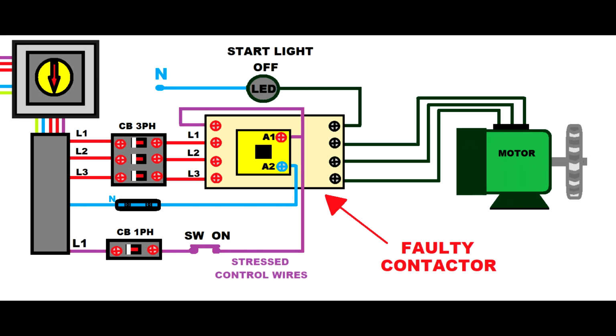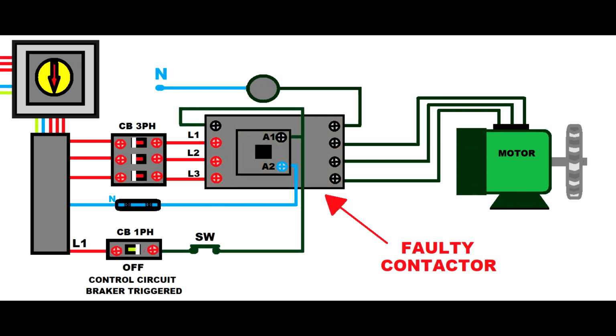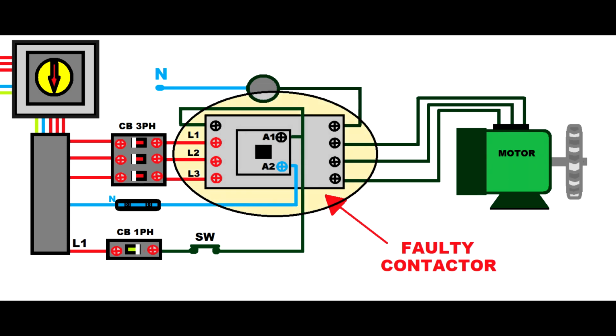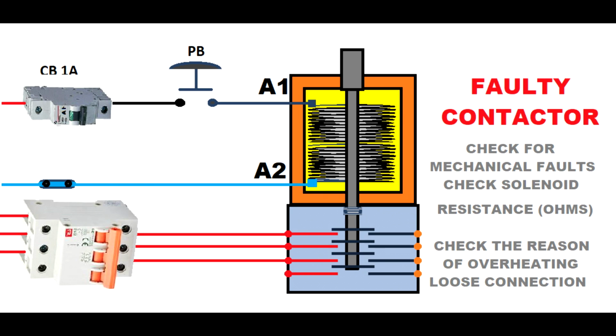Why would that happen? It could be a solenoid burn, it could be a mechanical fault of the contactor, it could be anything, but that will put stress on the control wires, and the circuit breaker of the control circuit might trip because you might have a short circuit on the contactor's solenoid, and the right thing is for the circuit breaker to trip. What do you have to do in this case? You have to check the contactor.